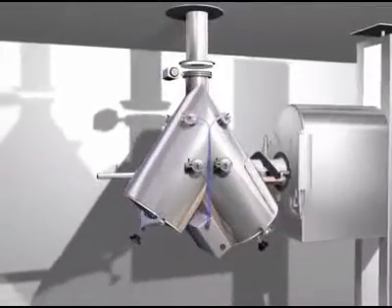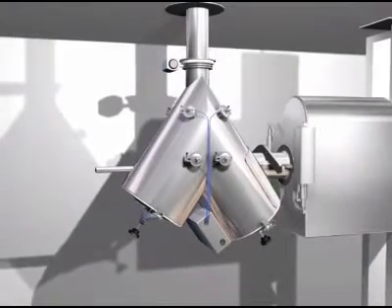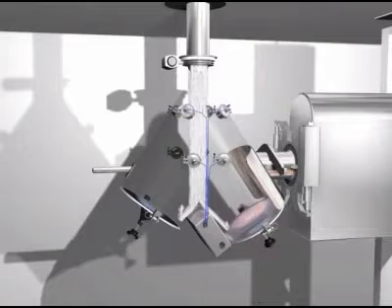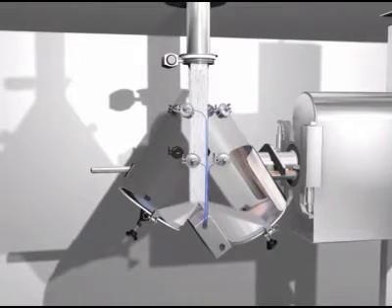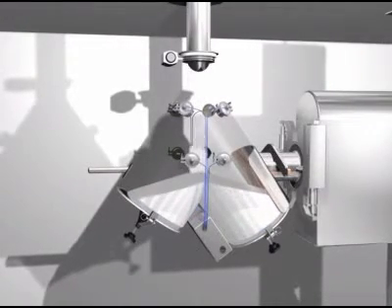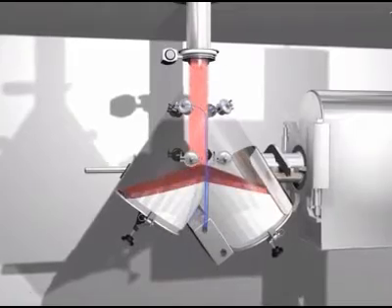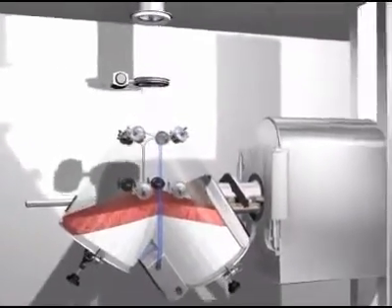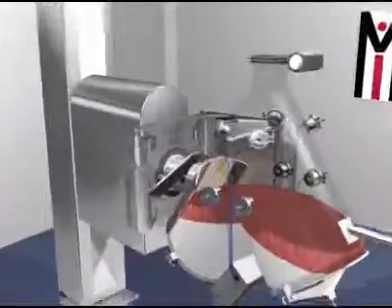The Mathis sensors operate very much like the way a human hand can differentiate wood and metal based on touch. Multiple sensors that are placed in contact with a uniform powder will give the same effusivity result. If those same sensors are in contact with different powders, effusivity results will vary.